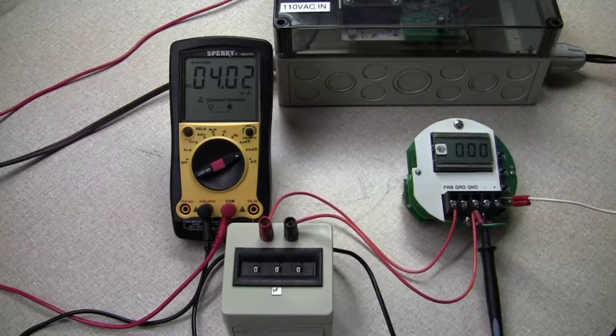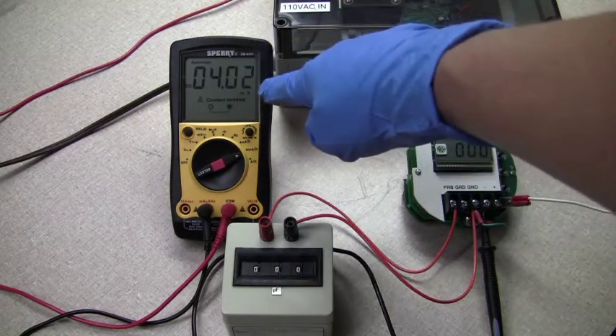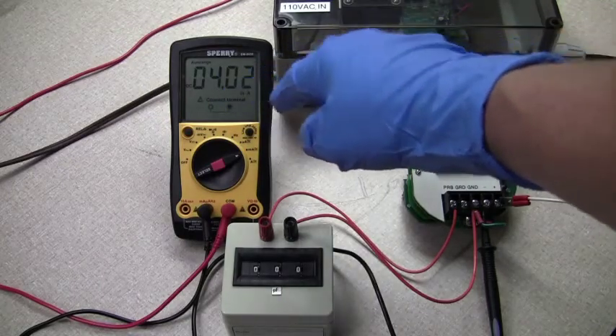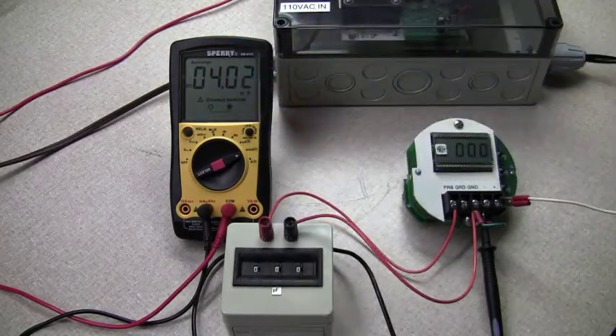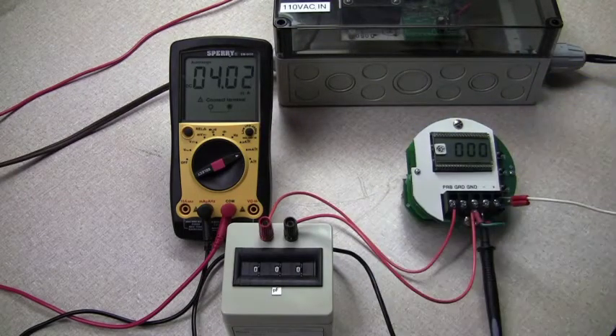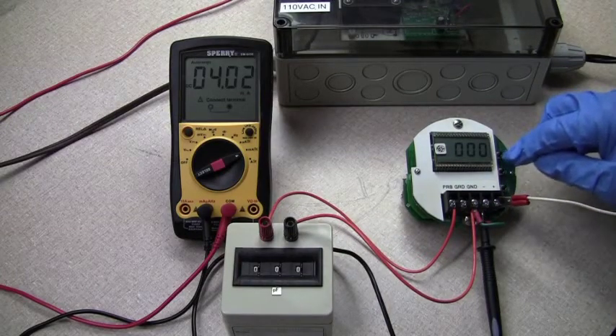So the first step is calibrating your 4 and your 20. The 4 and the 20 is very important. Right now as you can see it's already calibrated as we have 4.02. It could be 3.86, it could be 4.19 and this is how you're going to set up your 4 to 20. So these three buttons are what you're going to use to calibrate the unit, set your high and your low and your 4 to 20.